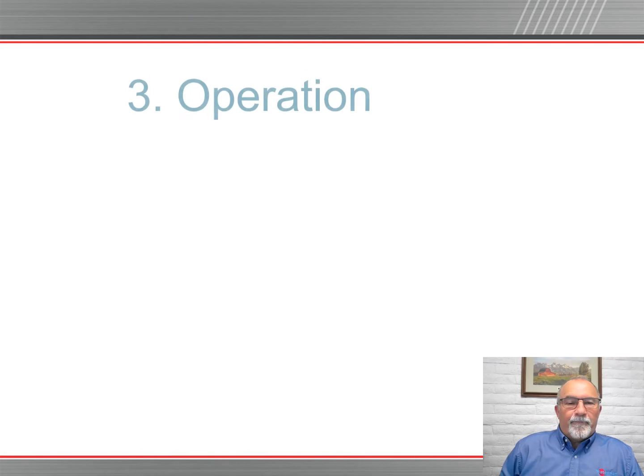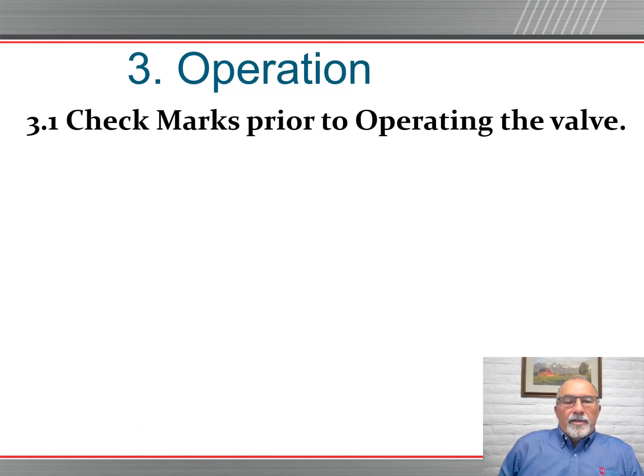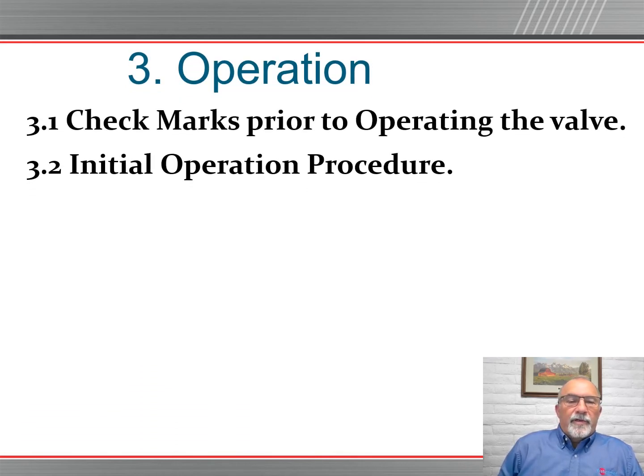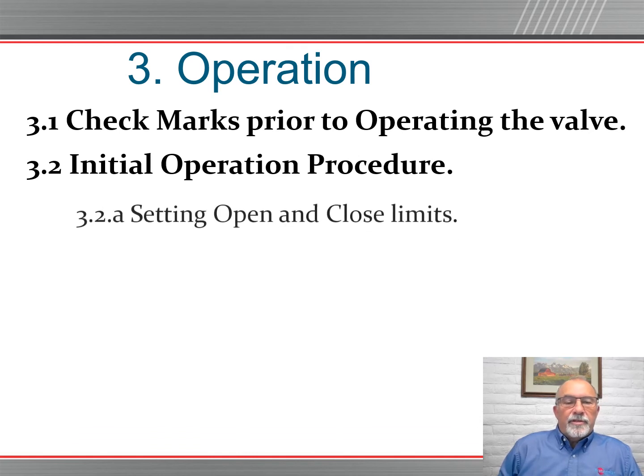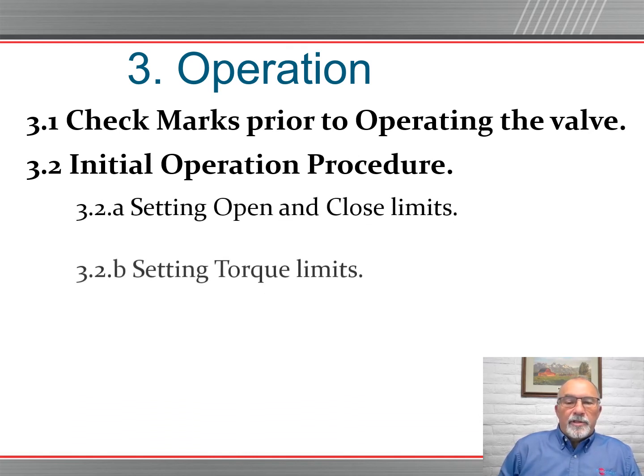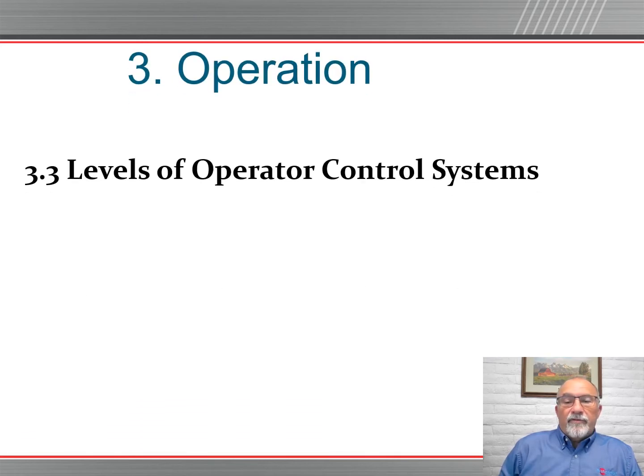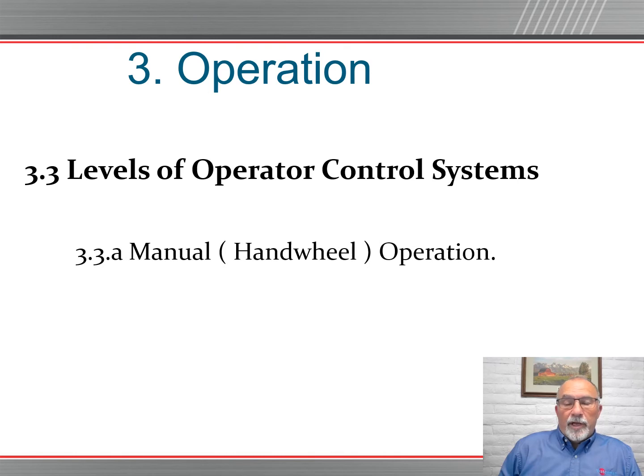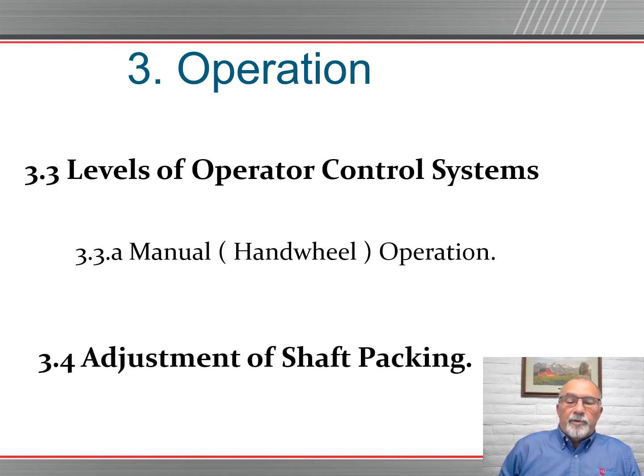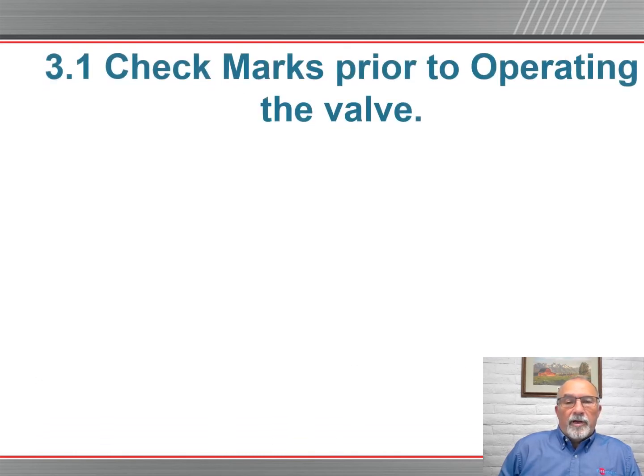Check marks prior to operating the valve. Initial operation procedures, setting the open and closed limits on your manual operator, setting torque limits are all going to be included in this section. Levels of operator control systems, manual hand wheel operation, adjustment of the shaft packing are all going to be covered.